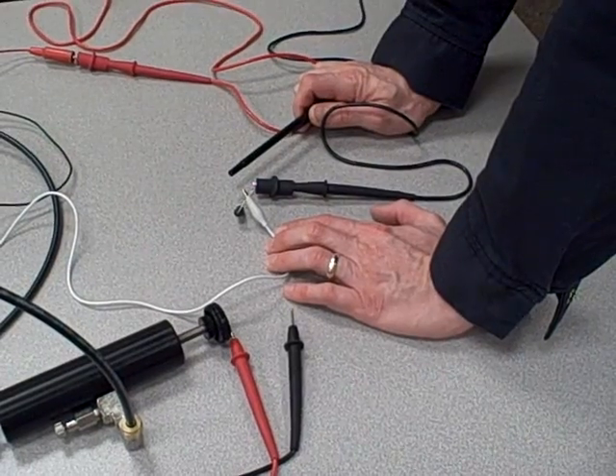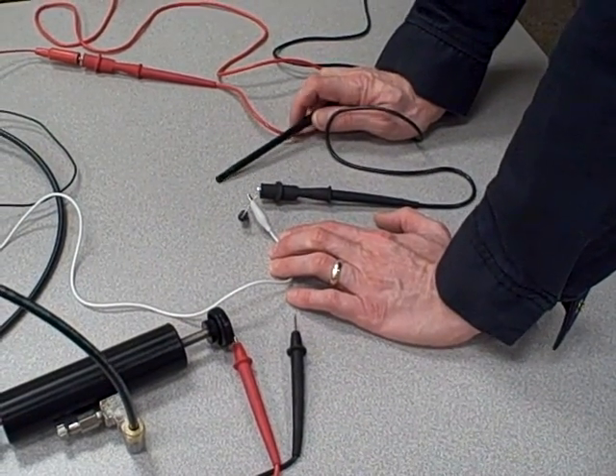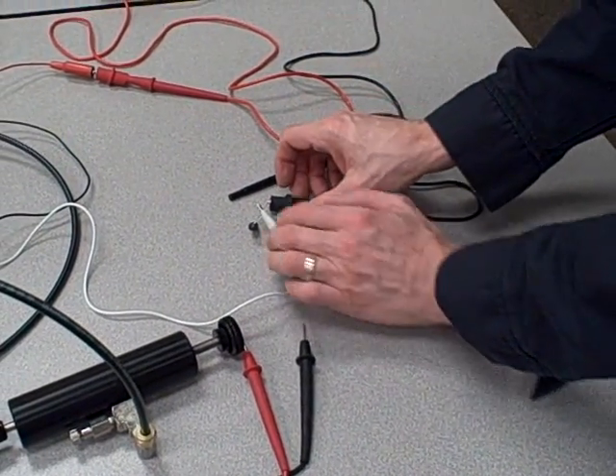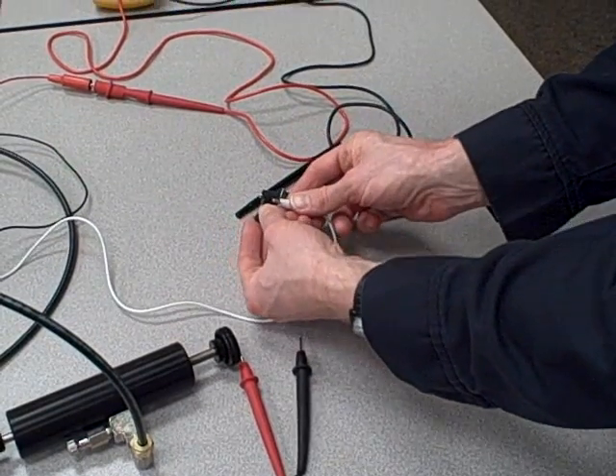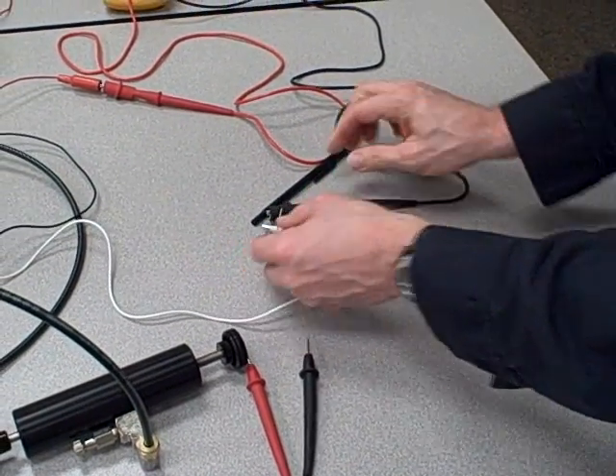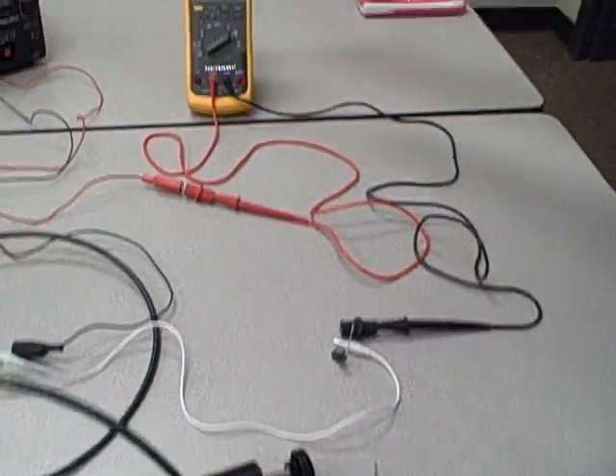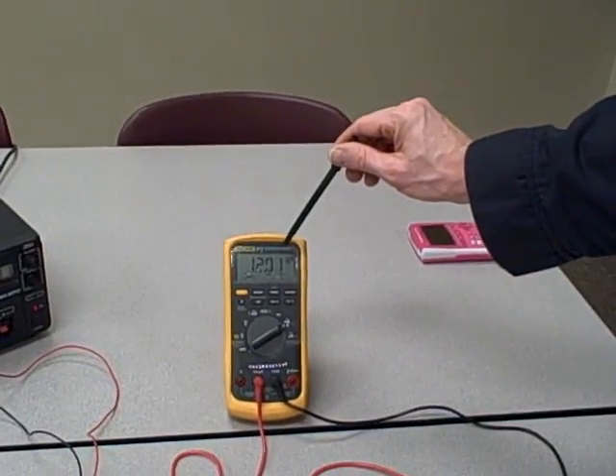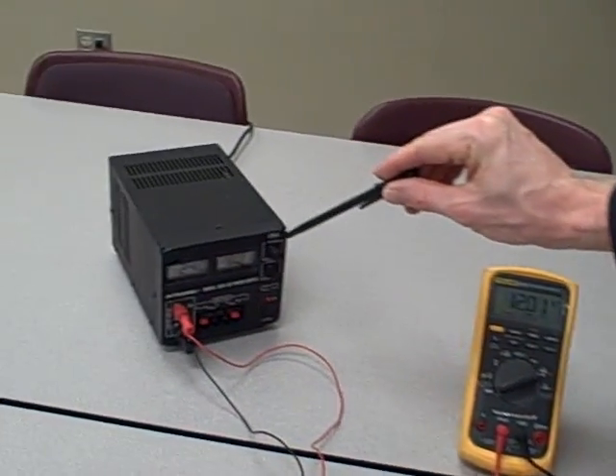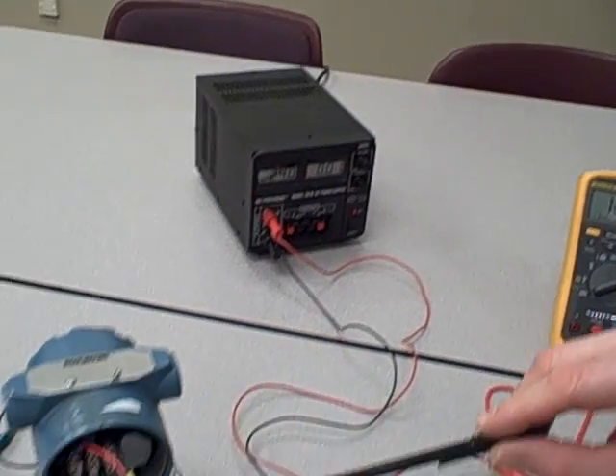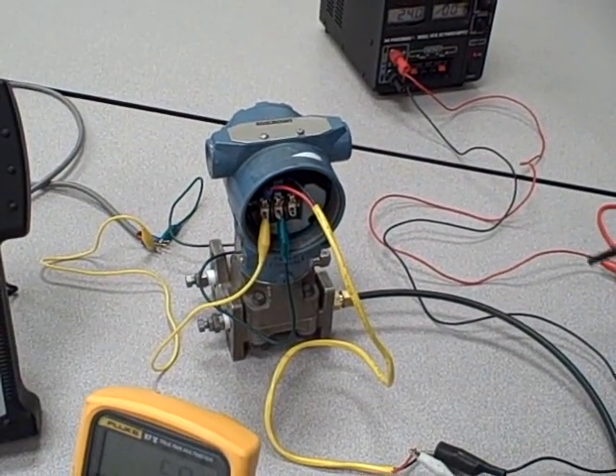If it does not, the HART communications will cease. I'll demonstrate this here. I'm going to take this 250 ohm resistor and bypass it. Notice my DC current is still 12 milliamps. I still have 24 volts supplied from the power supply. The pressure transmitter still has about 500 inches of water column pressure.